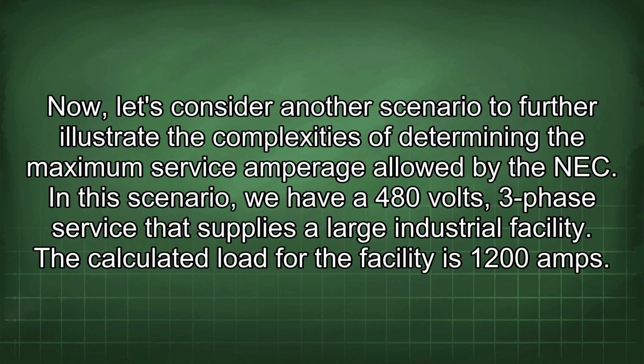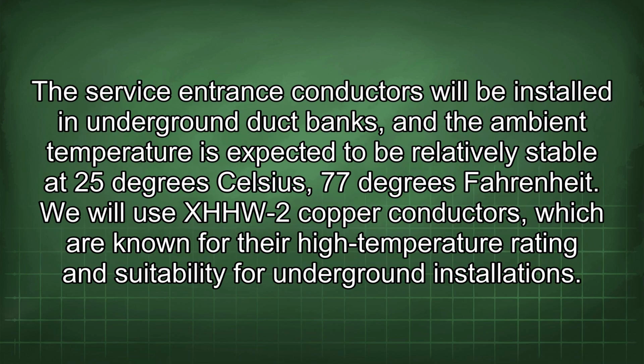Now let's consider another scenario to further illustrate the complexities of determining the maximum service amperage allowed by the NEC. In this scenario, we have a 480 volt, 3-phase service that supplies a large industrial facility. The calculated load for the facility is 1200 amps. The service entrance conductors will be installed in underground duct banks, and the ambient temperature is expected to be relatively stable at 25 degrees Celsius, 77 degrees Fahrenheit. We will use XHHW-2 copper conductors, which are known for their high temperature rating and suitability for underground installations.